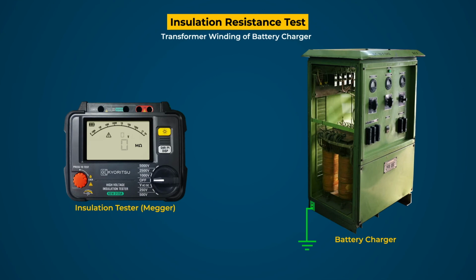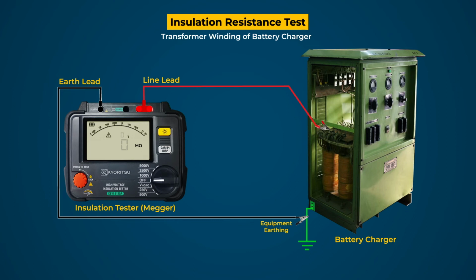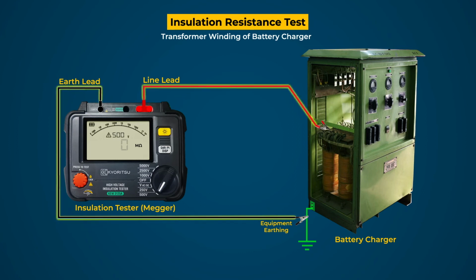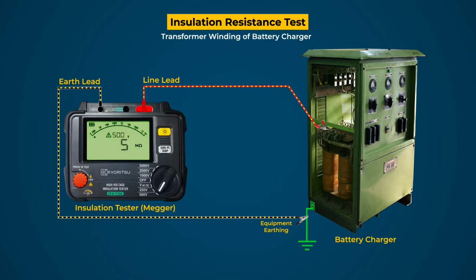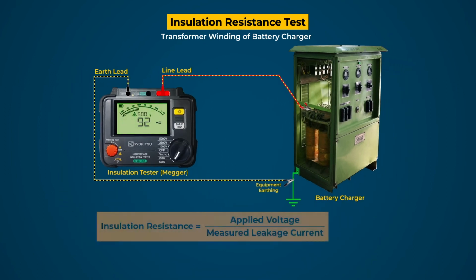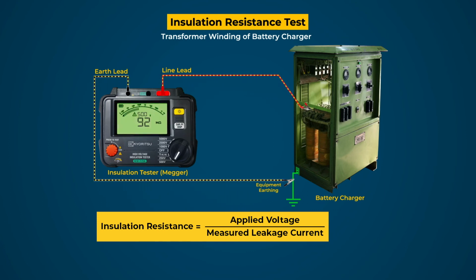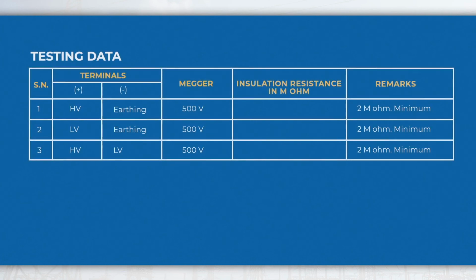Steps for testing. Here we are conducting a test for HV to earth. Now connect the line and earth terminal of the tester to the HV terminal and equipment earth through leads respectively. After that, check all the connections and select the test voltage level to 500 volt. Now on pressing the test button of the tester, 500 volt DC voltage is applied across HV and earthing. As a result, leakage current will flow in the circuit and the tester will measure this leakage current and calculate the insulation resistance by the ratio of applied voltage and measured leakage current. Do the test for these combinations and testing data may be recorded in this format for further investigation and future reference.